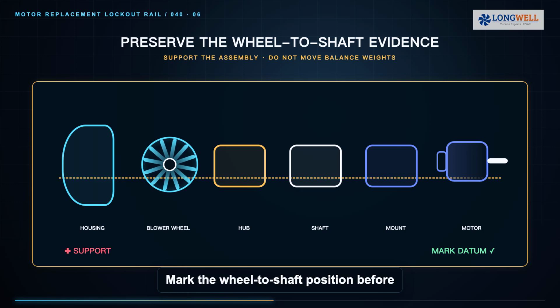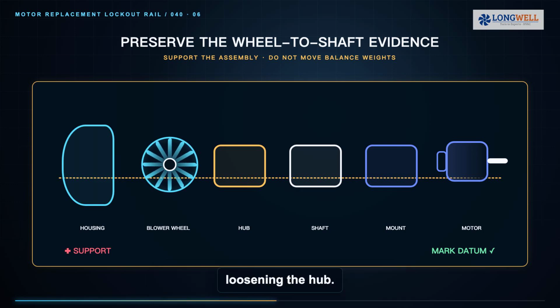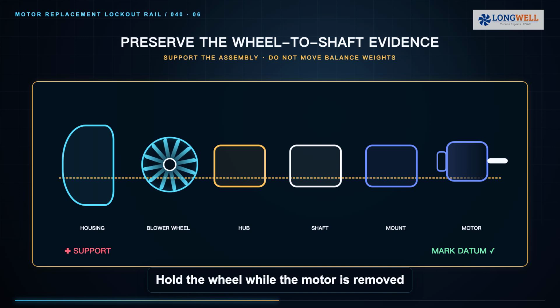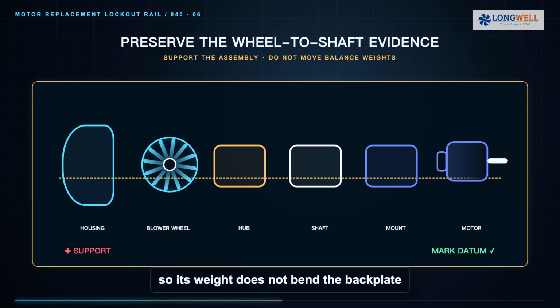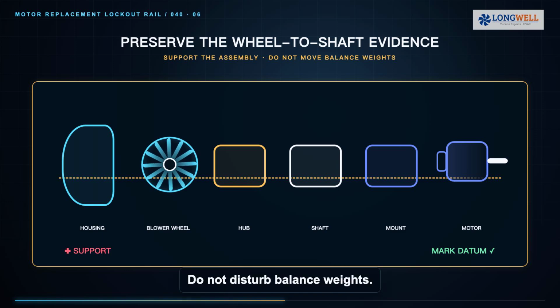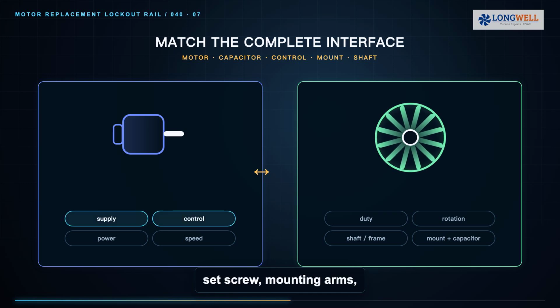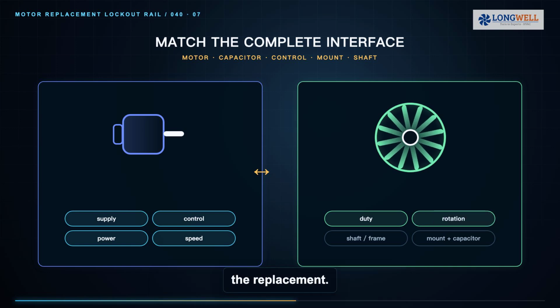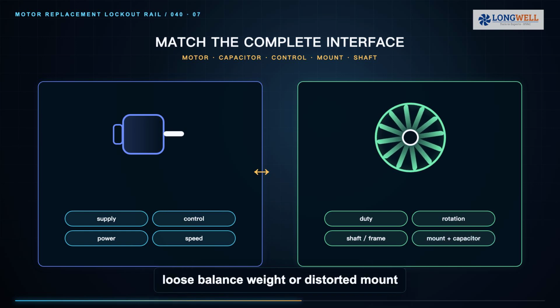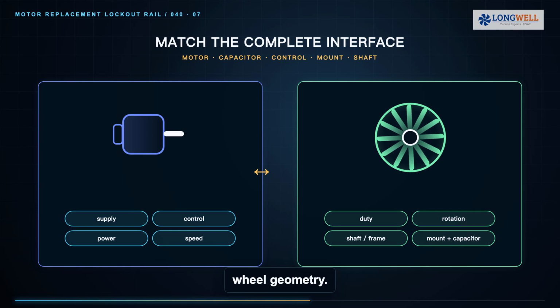Mark the wheel-to-shaft position before loosening the hub. Hold the wheel while the motor is removed so its weight does not bend the backplate or inlet cone. Do not disturb balance weights. Inspect the wheel, hub, set screw, mounting arms, isolators, and housing before installing the replacement. A cracked hub, bent wheel, loose balance weight, or distorted mount can recreate noise and vibration with a healthy motor. Clean accessible buildup without changing wheel geometry.